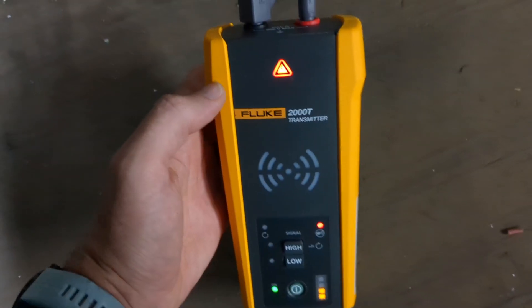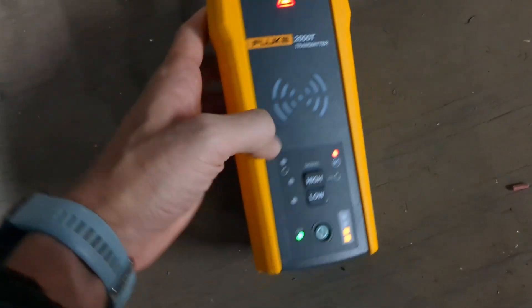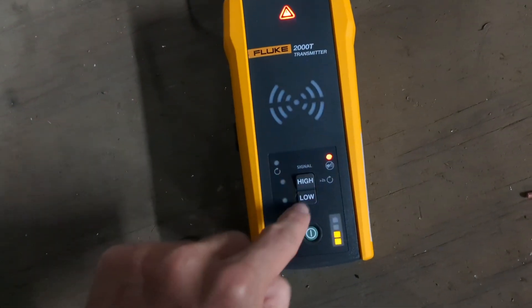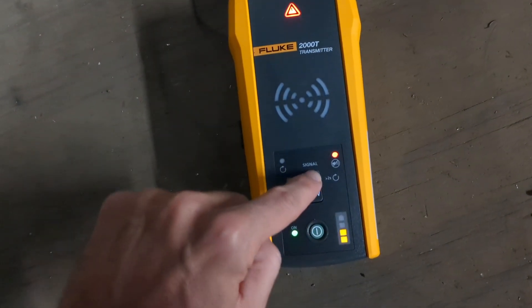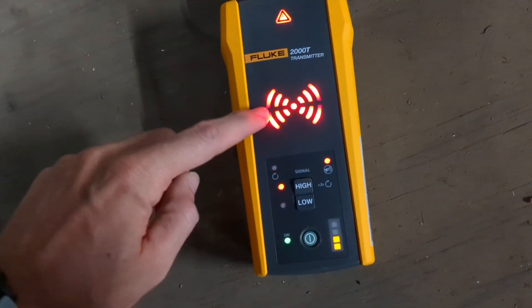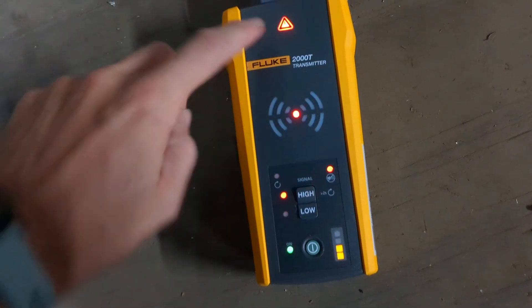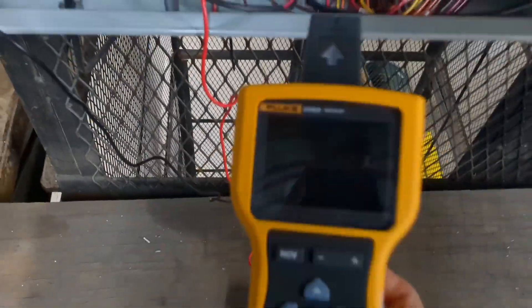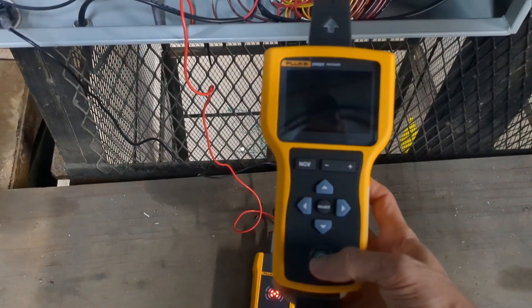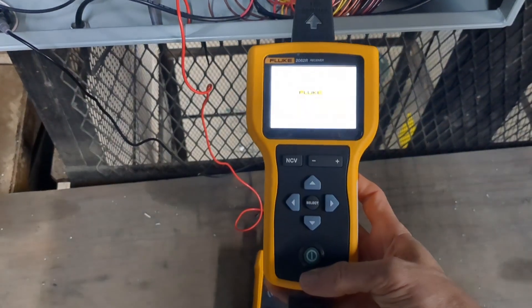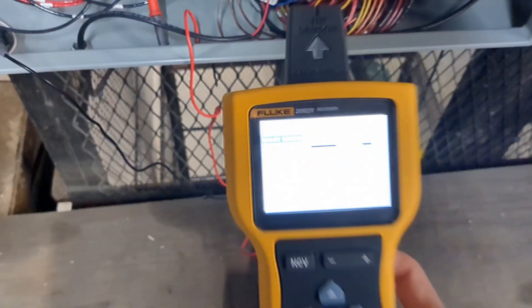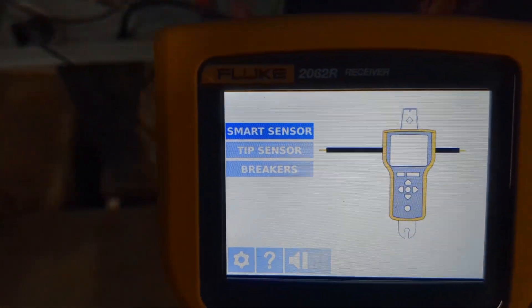This is a smart transmitter so it will send one kind of signal if it's an energized circuit and a different kind of signal if it's a de-energized circuit. You'll notice that says energized with that little triangle lit up there. Later on the receiver we're going to show you that it is receiving the signal for an energized circuit.